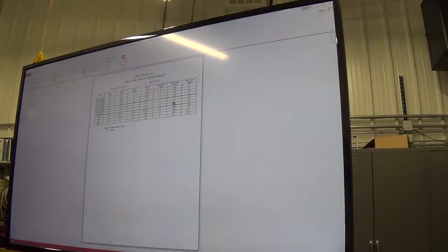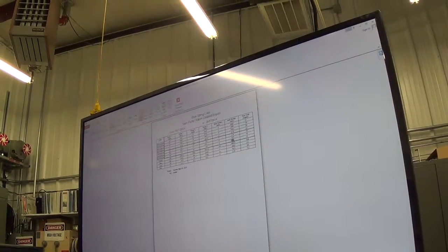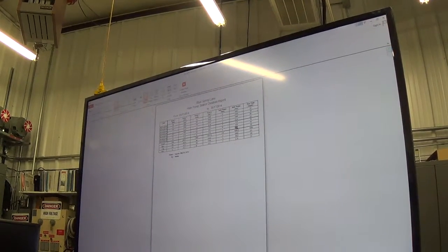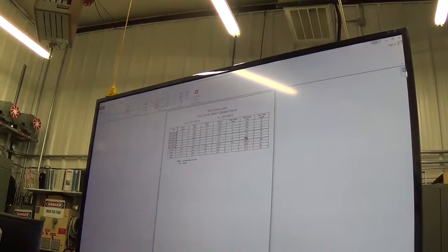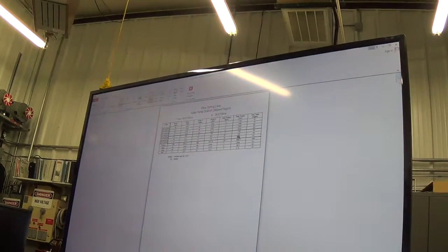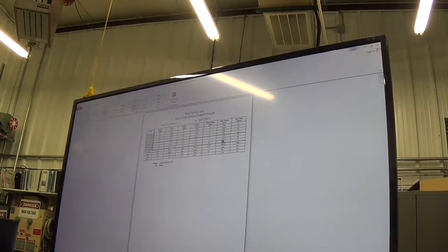I'm having trouble picking up some of the background conversation on the speakerphone, but your total 1,000 per day gallons, when that totalizes at the bottom of the sheet, is that actually taking your numbers, 31, 10, 20, 22? Is that rounding each day and then adding those, or is that actually totalized flow? If it's 31,212 gallons, is it adding that 212 as well, or is that just a rounded off flat 31?